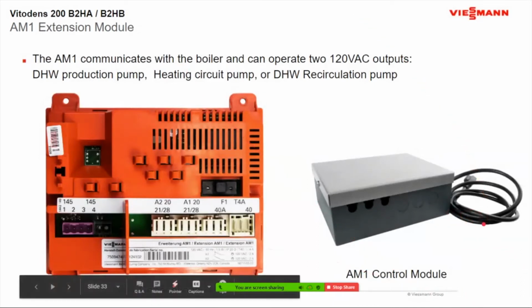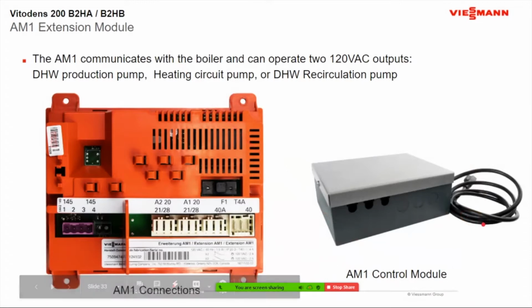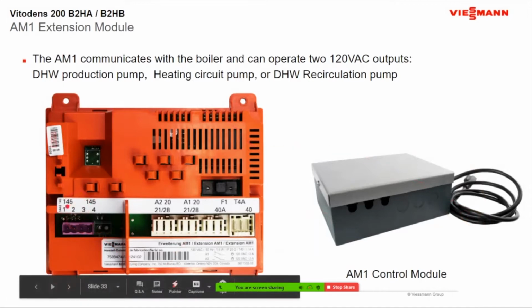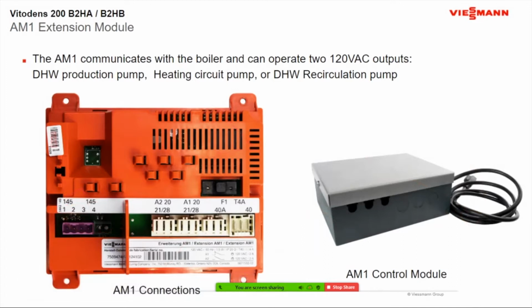Mixing valve, as you'll see, is pretty much the same type of box, just a different kind of setup here. But now you can see you can add more pumps, and now you're just going to send that 145 communication down at the bottom of the control. That 145 goes from here to that 145 communication. We now know that we have an AM1 module hooked to the boiler, auto recognized.